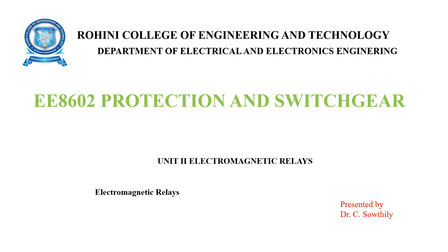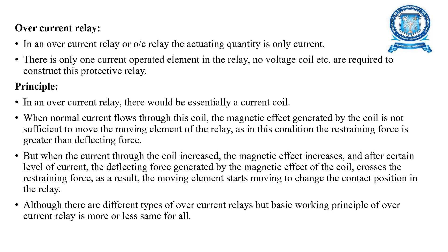We'll discuss electromagnetic relays. First is the overcurrent relay, where the actuating quantity is only current, so there is only one current-operated element in the relay with no voltage coil. The main principle is that a current coil is present. When current flows normally through the coil, the magnetic effect is not sufficient to move the moving element, but when current increases, the magnetic effect increases, and after a certain level the deflecting force crosses the restraining force.